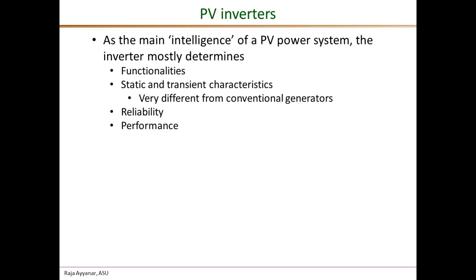In terms of reliability, the entire PV power system reliability is dominated by the reliability of the inverter and its components, because the PV modules themselves are highly reliable — they have 25 to 30 years lifetime. So a poor design of the inverter can bring down the reliability of the entire system.